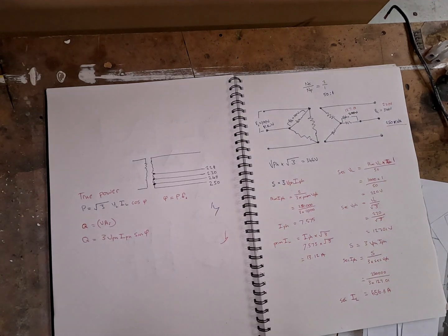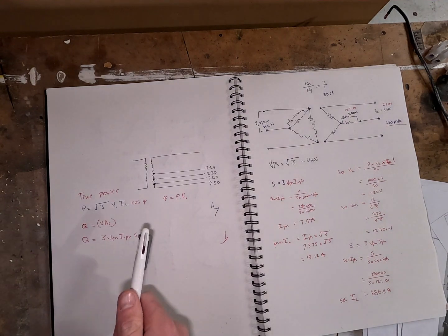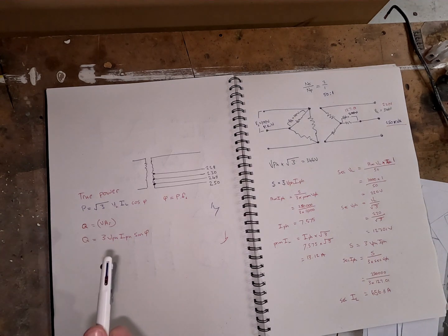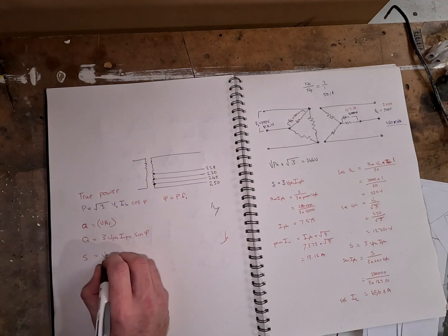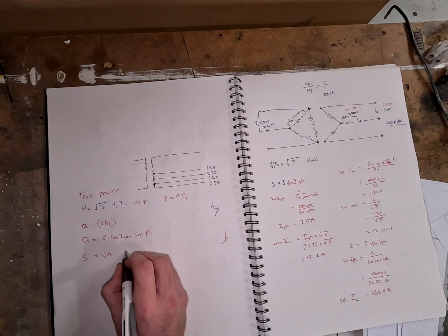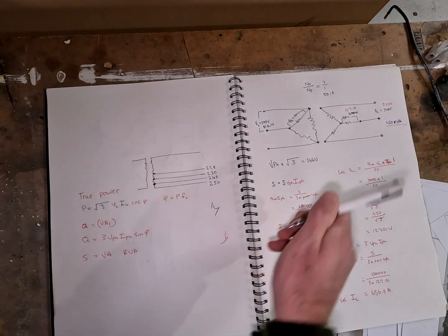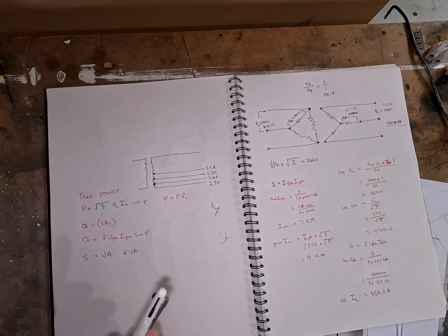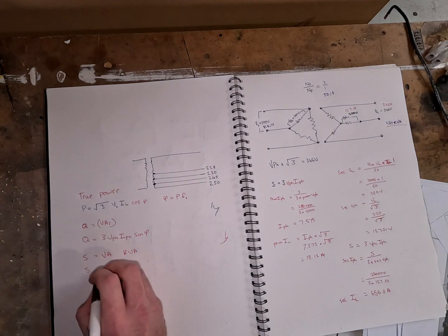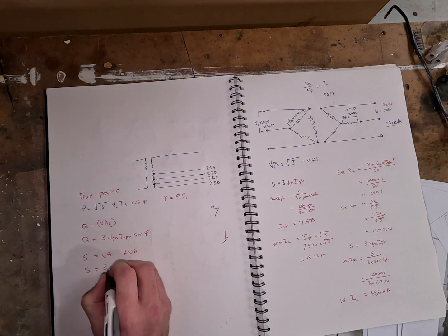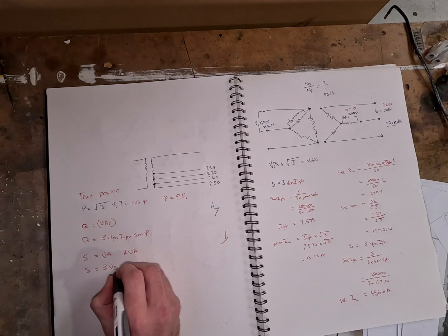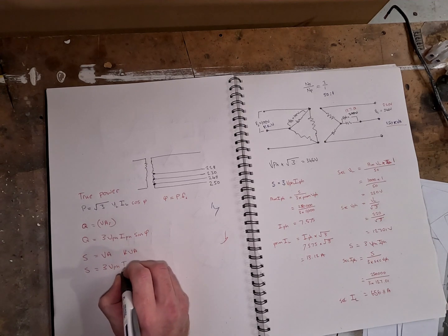Last we have apparent power, also the product of voltage and current, measured in volt amps or kVA, like our transformer over here. The formula to find S is 3 times the phase voltage times the phase current.